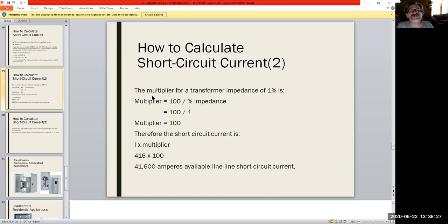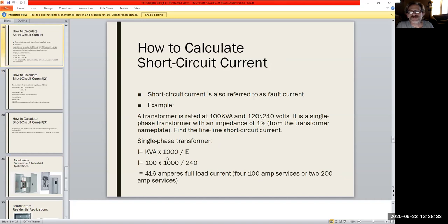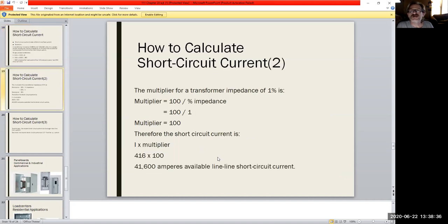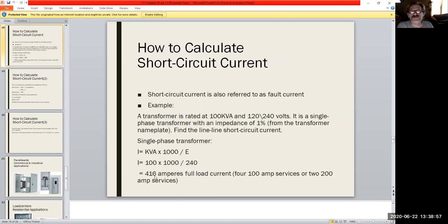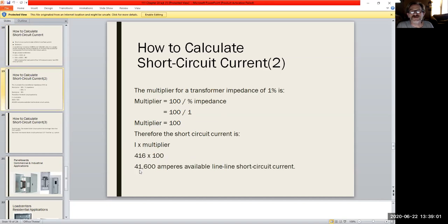So taking a look a little further at some of the math for this. And again, remember, all this is Ohm's law, a very straightforward application of it. We're not doing anything real fancy. Now, if we look at what our transformer impedance is, in this case, you get a multiplier of 100 over the percentage of the impedance, which in this case is 1. So our multiplier became 100. Therefore, our short circuit current is the current we got previously, the 416, times the 100. And what this does is it shows you that you have 41,600 amps available for line-to-line short circuit current. So this would be your maximum rating involved. And this is the rating your equipment would have to have to be fully certified to be used for this particular service. Does that make sense? I hope.